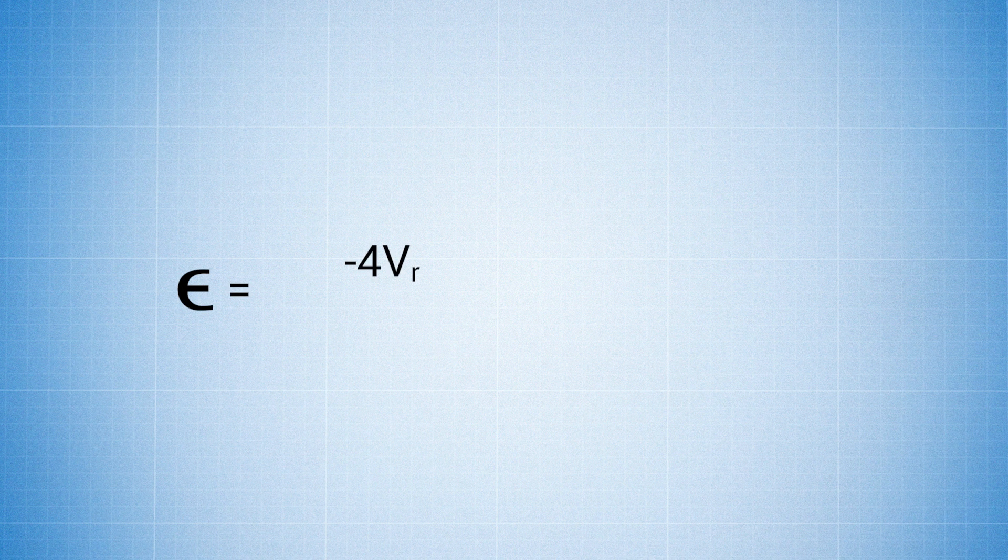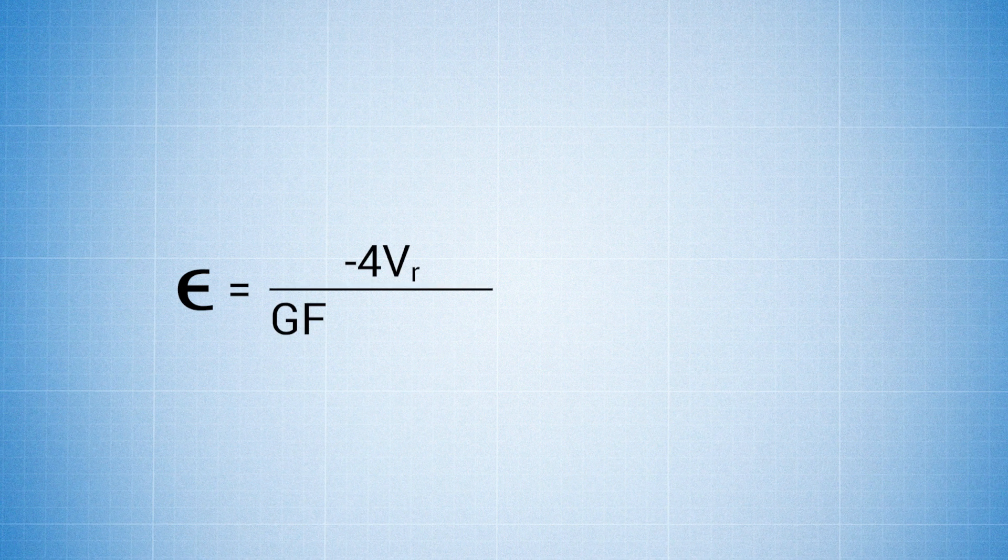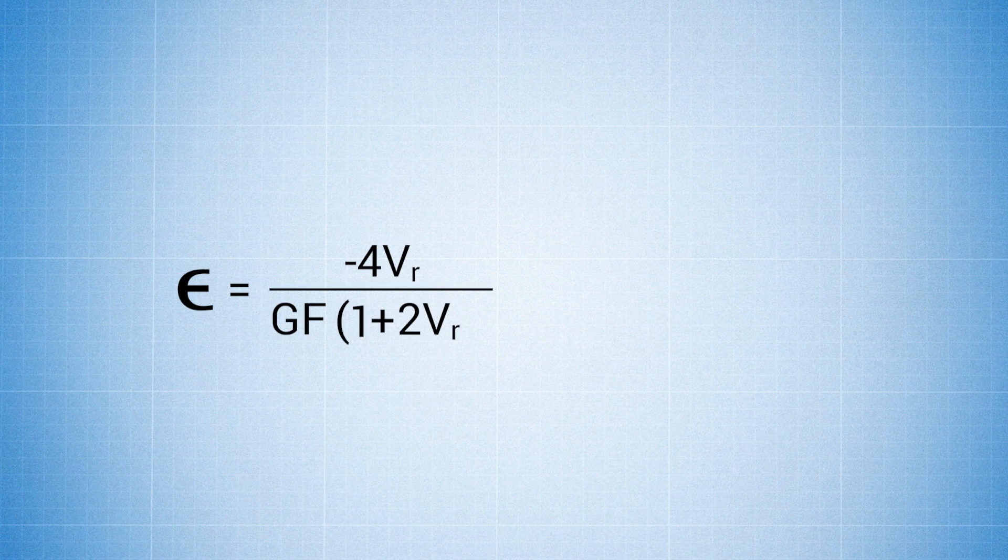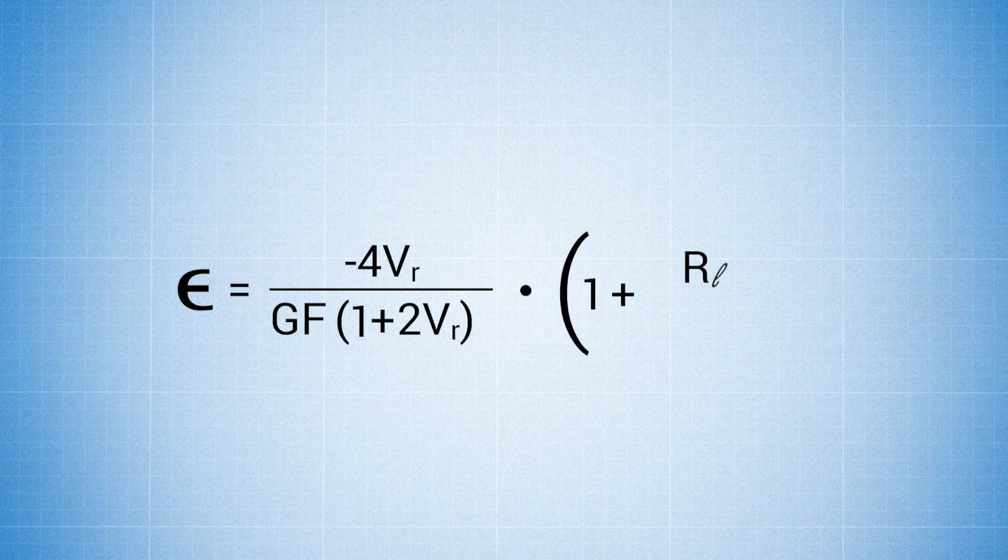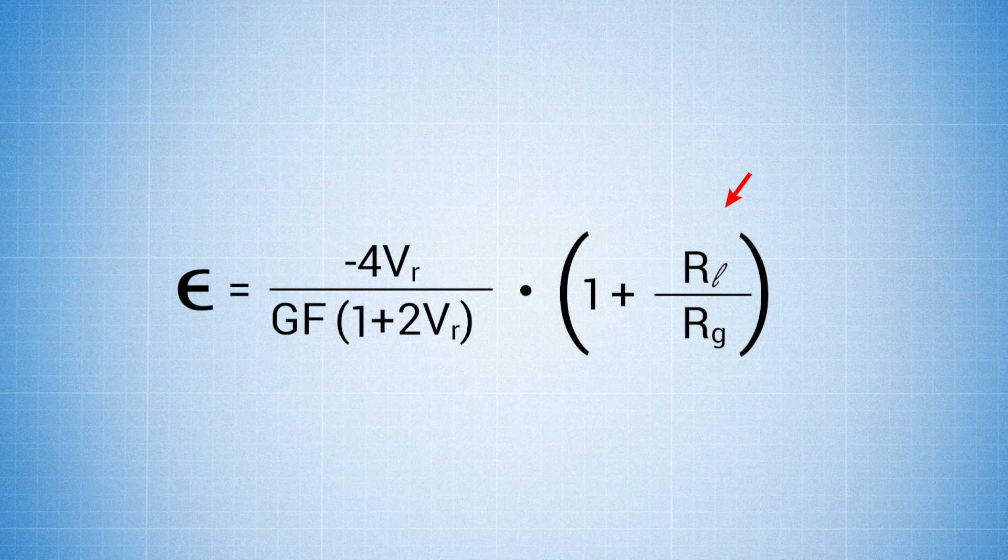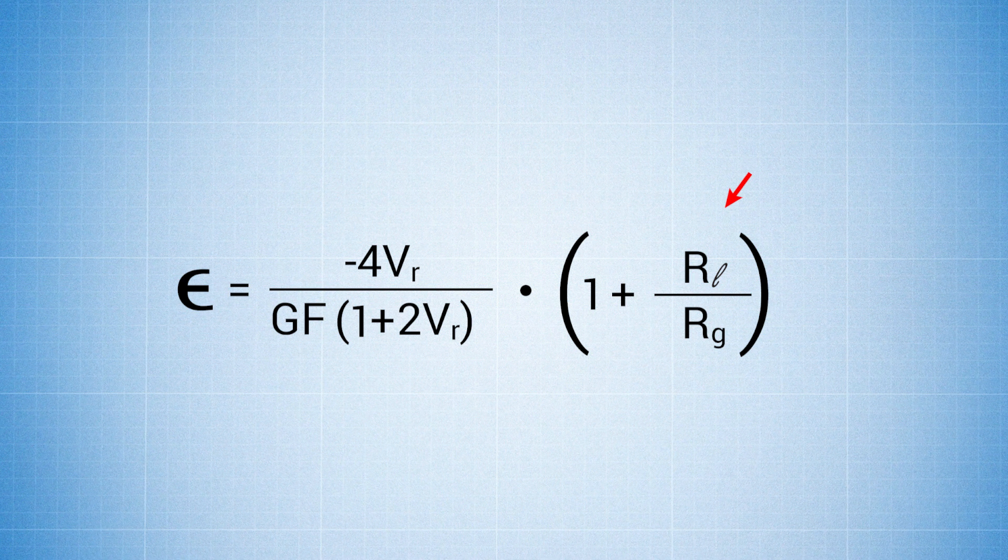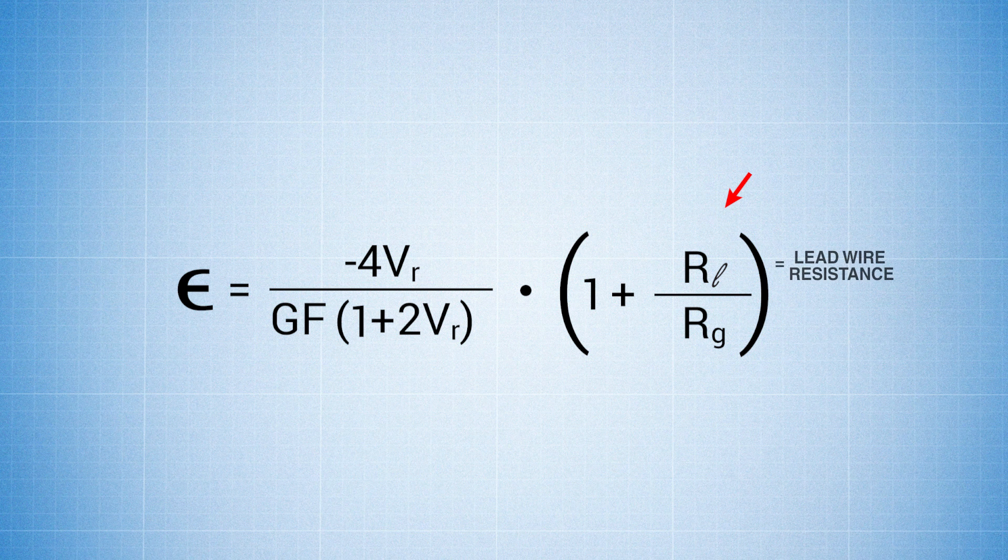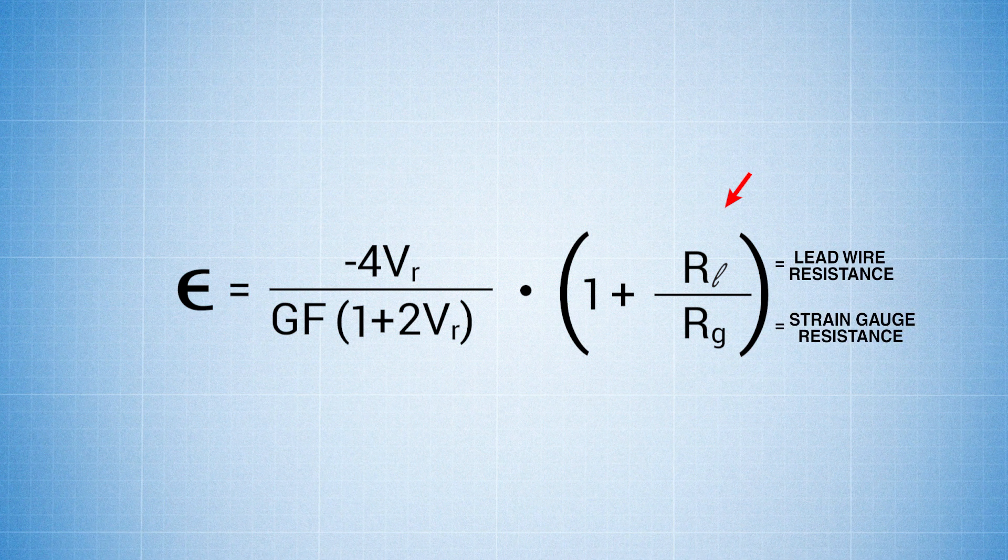Now let's look at the formula we'll use to calculate microstrain. Epsilon equals negative 4Vr over GF times 1 plus 2Vr, multiplied by 1 plus Rl over Rg. In the parentheses where you have 1 plus Rl over Rg, Rl indicates lead wire resistance and Rg indicates the resistance of the strain gauge.